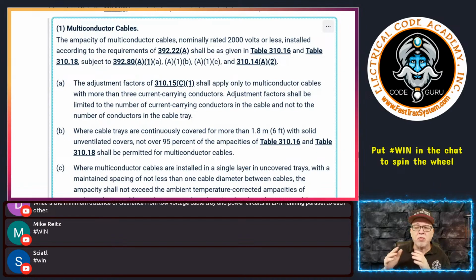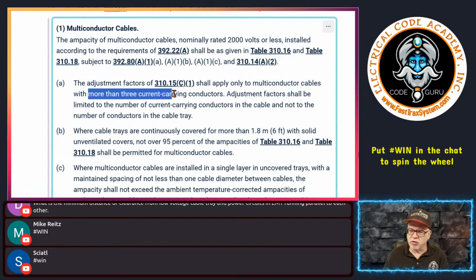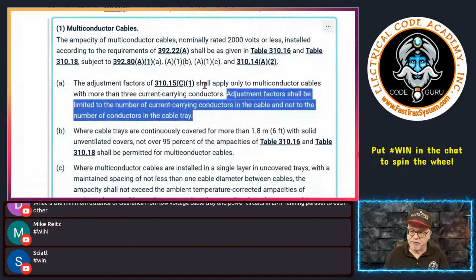So don't think that that's gone, because that still is there. That always is there. So it doesn't remove that requirement, but it's specifically removing the number of current carrying conductors as long as each cable doesn't exceed 3 current carrying conductors, okay? And it may or may not exceed 3 depending on, let's say you have a tray cable with 4 conductors in there, three hots, if you will, and a neutral. If that neutral is considered a current carrying conductor, then guess what? It will exceed 3. And if that's the case, then 310.15(C) does apply. Make sense? Okay. So you only get to remove this if the cable doesn't have more than 3 current carrying conductors. If it does have more than 3 current carrying conductors, then you must take into account 310.15(C)(1). Okay. All right. And again, this last statement here only comes into effect if you meet the first statement here.